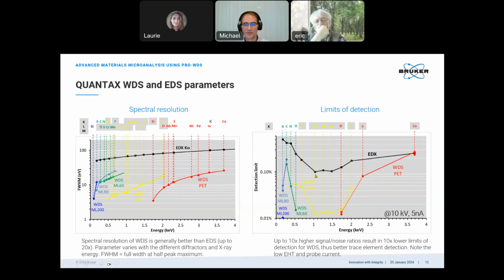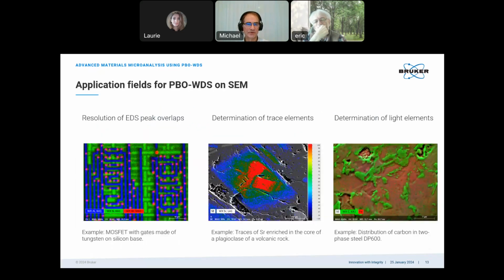So the minimum amount for EDS is 0.1% as detection limits, and we are 10 times better with the WDS. So we can determine traces of 100 ppm even for light elements. So even for the very low X-ray energies, light element boron, we can detect traces of 100 ppm. So from this, we can conclude some applications which are very suitable for the WDS.